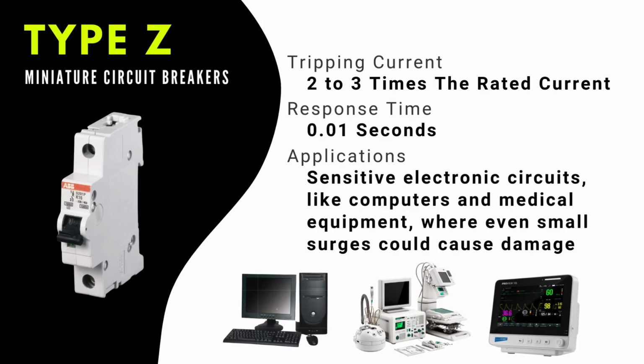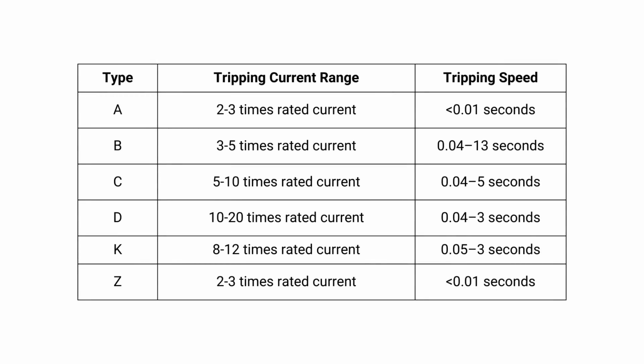To wrap it up, here's a quick comparison of all the MCB types we've covered. As you can see, each type is designed for specific applications based on the tripping current range and tripping time, from Type A's super-sensitive protection for delicate electronics to Type D and K for industrial machinery. Choosing the right MCB can make a big difference in keeping your circuit safe.